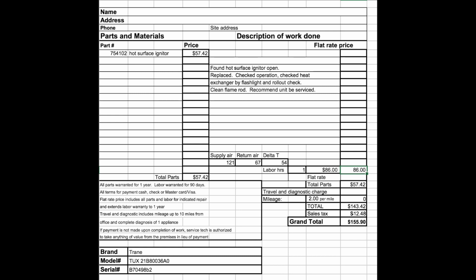It's electrically open, replaced it, checked operation. When you're checking operation, you're probably going to let it run through a few cycles, turn off the gas, make sure the safety's out, and I've checked the heat exchanger by flashlight and rollout check.